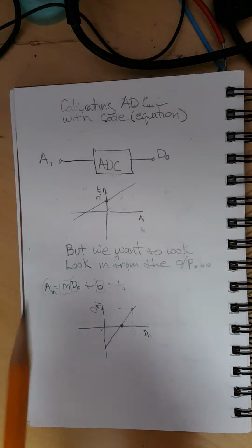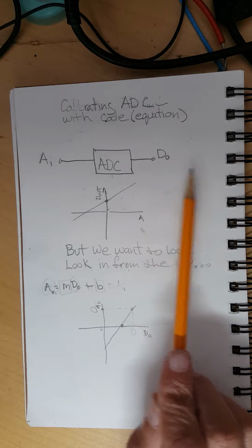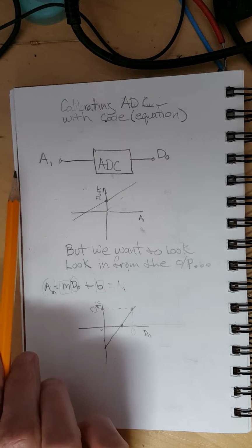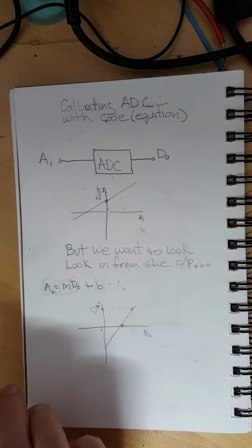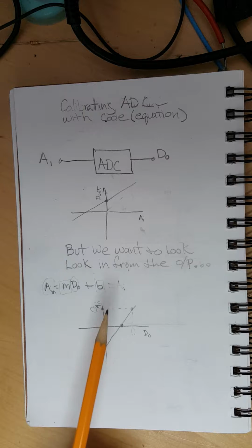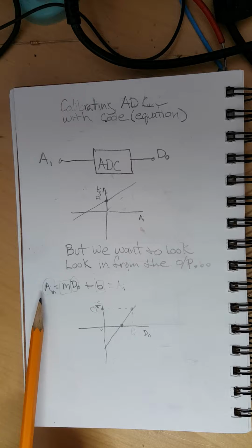Okay, this is a quick explanation of how to AutoCal an A to D converter, basically using code to adjust the output to match what's actually at the input. Typically, you'll do 2 points. You put in one input and you get a corresponding output, and then you put in another input and you get a corresponding output. And from that, you can come up with an equation which basically adjusts the output. D times what plus any offset will give you what's actually at the input.